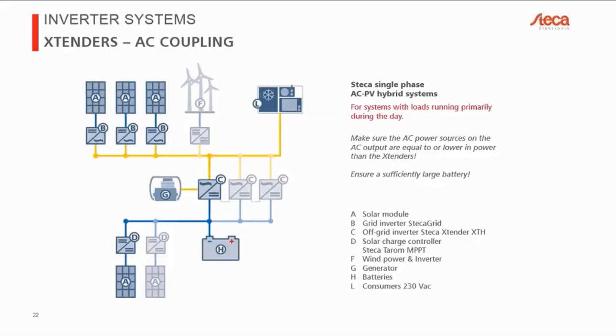And now, as a very final point, we need to keep in mind what happens when the system has too little energy, so when there's not enough sunshine, when the battery voltage is running low. There's a few things you can do. Either you can connect the loads, the AC loads, via a large AC contactor to one of the auxiliary relays of the Xtender, which you can program freely. So you can, for example, tell the relay to switch off the loads at, let's say, 42 volts. And then you still leave the AC grid running, the inverter running, so that PV can continue to charge the Xtender.